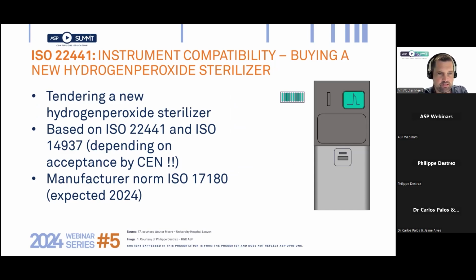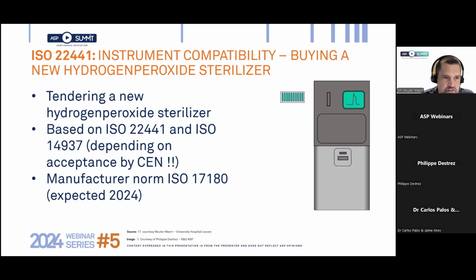Now the next thing is, I'm going to buy a new one. So there's a new norm. So how do I look at tenders? That means I'm tendering for a new hydrogen peroxide sterilizer. In this case, you can at the moment still use both ISO norms, the ISO 22441 and the ISO 14937. And of course, at a certain moment in Belgium already, the new norm is accepted. But on the EN side, it still needs to be generalized in the near future. And of course, if the 17180 is also approved and published, then again, you have some clear norms that you can put in your tender to make sure that if a manufacturer offers you a hydrogen peroxide sterilizer, it will be conforming and consistent with the new norms available for hydrogen peroxide sterilizers. Next slide.